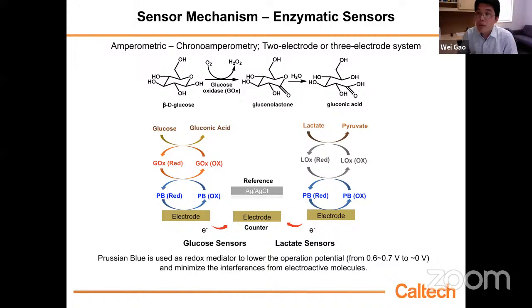This is the generation-one glucose sensor. Here we are using a generation-two glucose sensor. Instead of detecting hydrogen peroxide directly, we introduce a redox mediator, such as Prussian blue, which lowers the operating voltage of this glucose sensor to around 0 volts. Detecting hydrogen peroxide requires a high voltage, but if we use only around 0 volts, that minimizes the influence from many electroactive molecules in our body fluid.